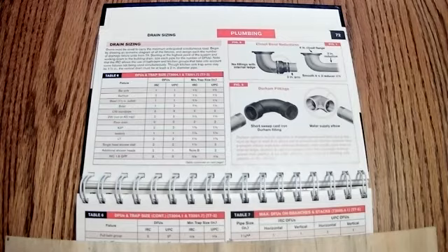And again, the IRC will allow you to have a 1.5 inch drain anytime you have basically a shower or anything. I would never, ever put anything on an inch and a half. Most of the shower drains come with a 2-inch tailpiece, so you really need to put on 2-inch pipe.